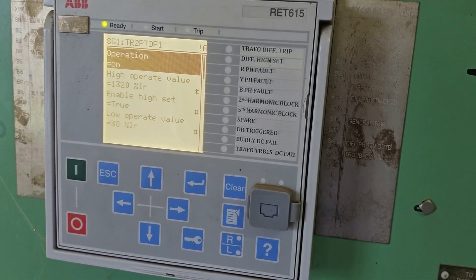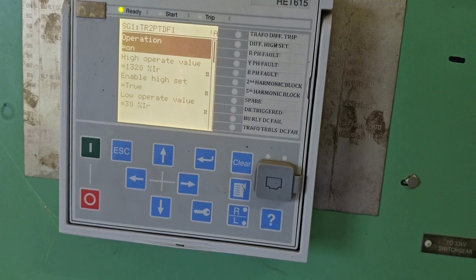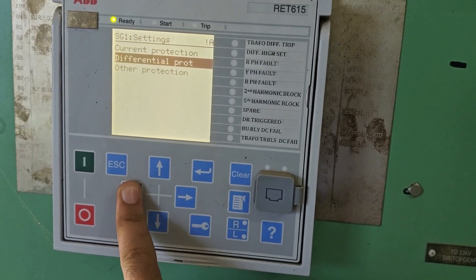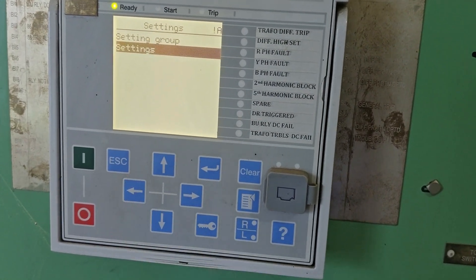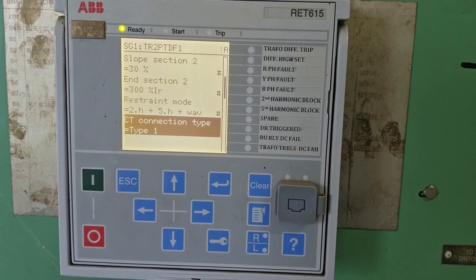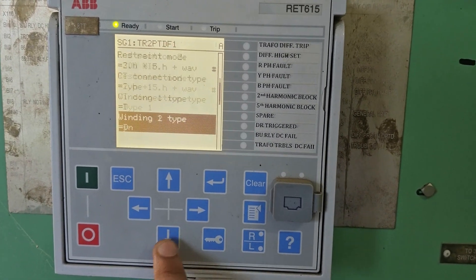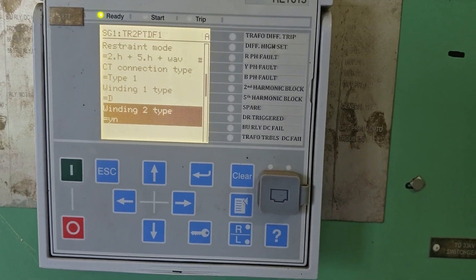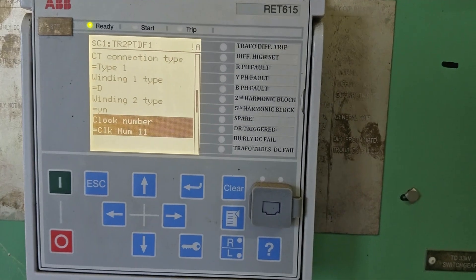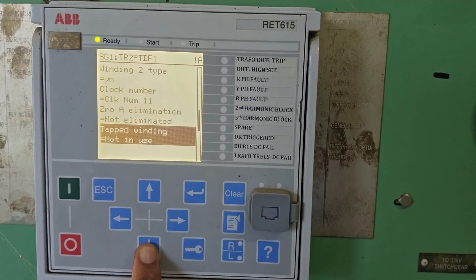For the vector group, as per the relay manual, we have set vector group 11 — the clock level. This indicates that the transformer LV is leading 30 degrees with respect to HV.